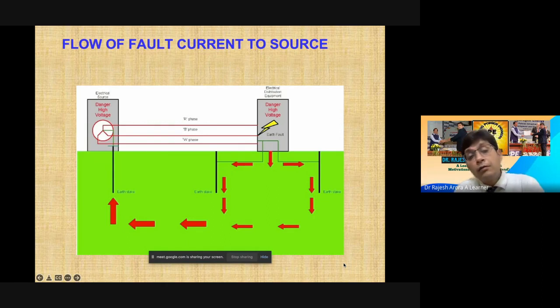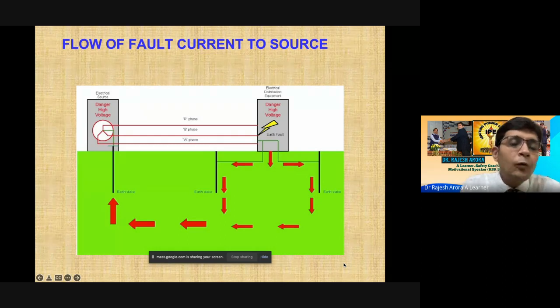Coming back to technical points, what happens when a fault happens and how that fault current in the system goes back up to the point of source is depicted in that picture. If you look at that picture, a fault happened and it took two paths, electrode 1, electrode 2, then it took help of that Mother Earth to go back to the source. And at the point of source, where the neutral of your generator or your transformer, whatsoever it may be, is connected to or inserted in the earth, it enters back to that earth to that point.